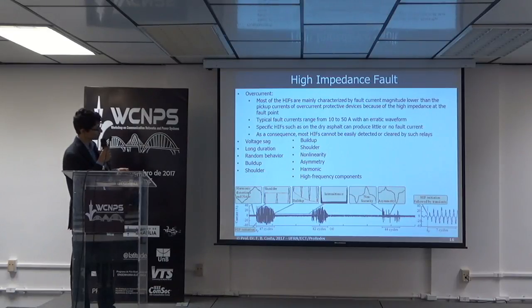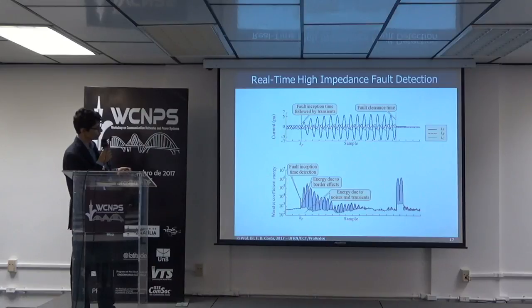For instance, here we have an actual case of high impedance fault. By using a conventional Wavelet Transform, the fault could not be detected. However, by using the boundary Wavelet Transform, a version of the Wavelet Transform, the high impedance fault could be detected successfully here.